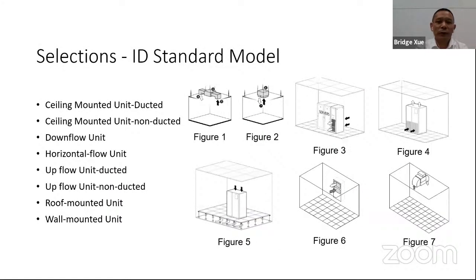For this slide, it's easy to understand: there might be different indoor unit types applied for the data center. The first is the ceiling mounting unit with ducted or without ducted. You can see the pictures in configurations one and two. Numbers three, four, and five are the traditional equipment used for data centers. The first is a downflow unit, the second is a horizontal flow unit, and the other is an upflow unit with and without ducting. The last two are the new equipment used for data centers: the rooftop mounted unit and the wall mounted unit.